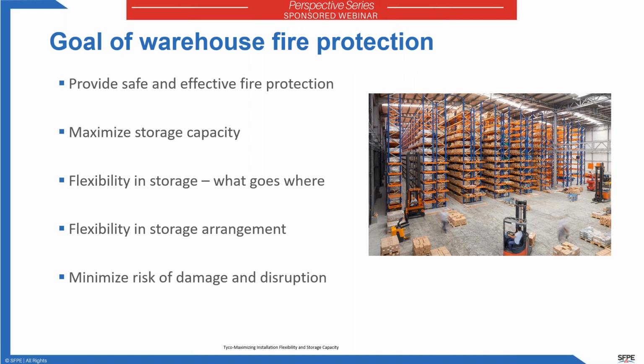Secondly, operators want flexibility. What goes where? We like to minimize having restrictions on where exposed expanded plastics can go, or even if you can have exposed expanded plastics or things of that nature. If you can have flexibility, the chances of something going wrong get significantly reduced. And then this type of storage arrangement: we'd like to be able to move racks as needed, as business conditions dictate. Flexibility in whether it's on the rack or palletized or high piled or stacked. I also want to minimize the risk of damage and disruption. When a forklift hits a sprinkler that might be in a rack, no one has a good day. So a significant goal that we have with warehouse fire protection is developing ceiling-only protection.